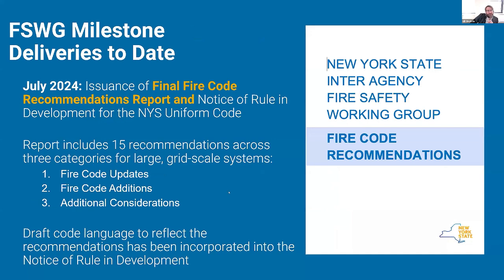In July of 2024, the final fire code recommendation report and the notice of rule development for the fire code were released, with the 15 recommendations included. They all only apply to large, grid-scale, front-of-the-meter systems. The fire safety working group did not set out to address residential or small systems—what we call behind-the-meter systems that service a local load. So all these recommendations and the corresponding code language should only apply to these very large systems feeding directly into the grid.